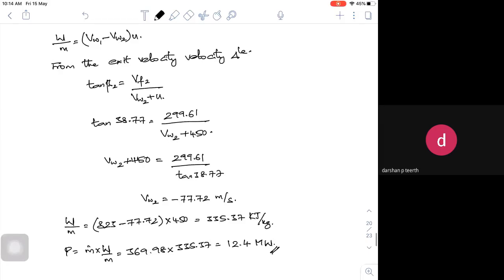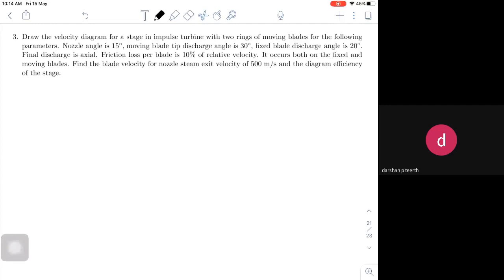Draw the velocity triangle for a stage in an impulse turbine with two rings of moving blades for the following parameters: nozzle angle 15 degrees, moving blade tip discharge angle 30 degrees, fixed blade discharge angle 20 degrees, final discharge is axial. Friction loss per blade is 10 percent of relative velocity, occurring on both fixed and moving blades. Find the blade velocity for nozzle stream exit velocity of 500 meters per second and the diagram efficiency. Take speed ratio as 0.45.